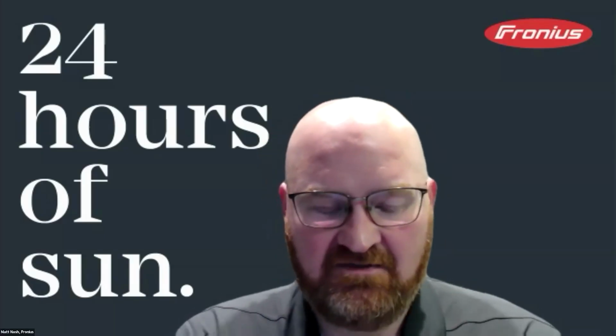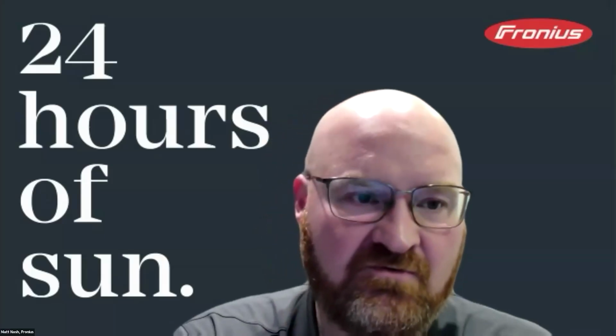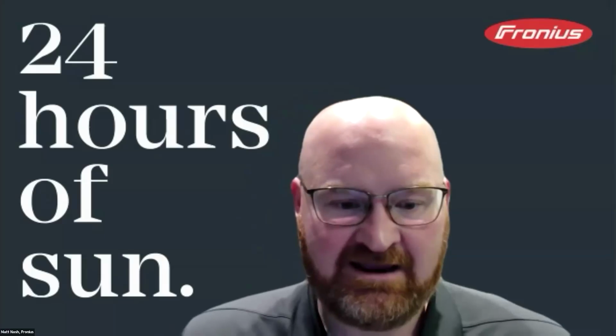That's awesome. There's also a somewhat related question from the audience. So if you could elaborate again on the major differences between the last generation inverters and the Gen24 when installing, with a particular focus on replacement purpose. Okay. So if we're talking about replacing a power class with a like power class, the biggest difference is the no torque requirements. The previous generation did require torque specs on everything, from the terminal block to mounting the inverter to the mounting bracket to closing it up with the DATCOM cover. That's a lot of time that gets consumed, which also gets passed down to the customer with labor cost. So the fact that you can actually install the inverter without having to worry about breaking out a torque driver is the biggest upside to the previous generations.